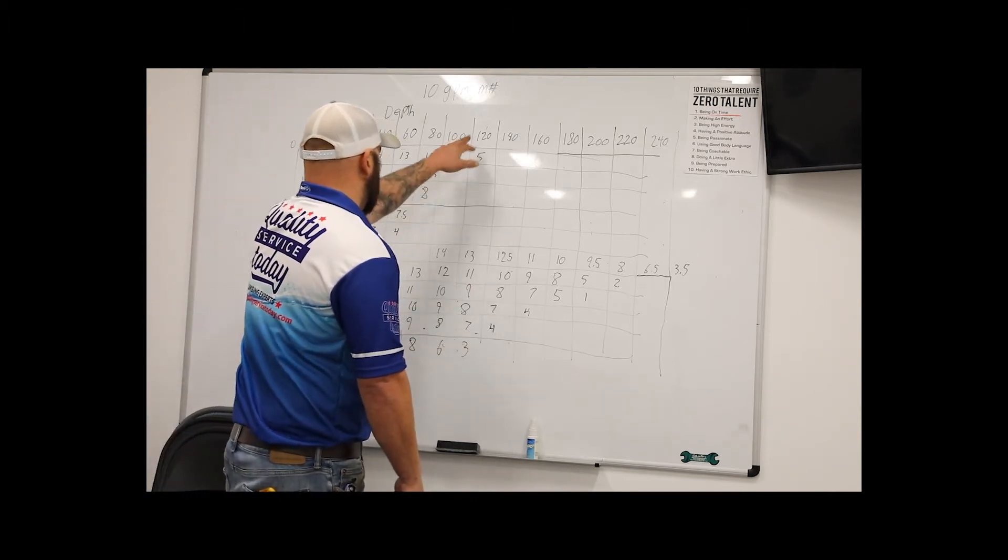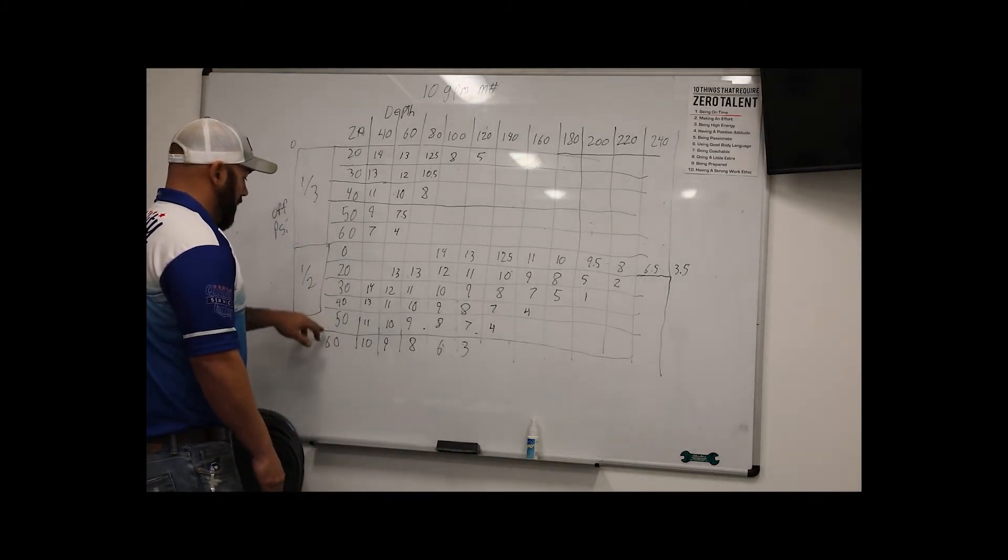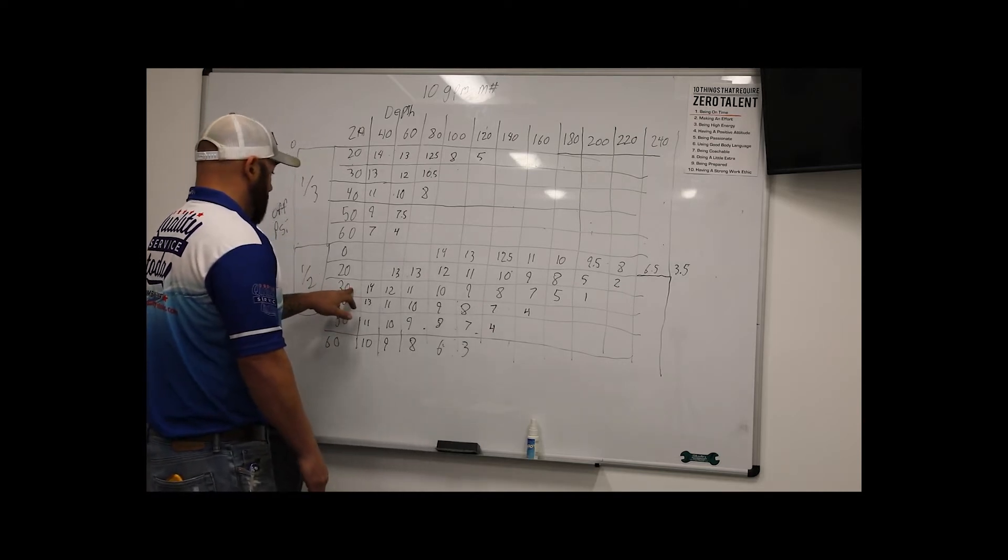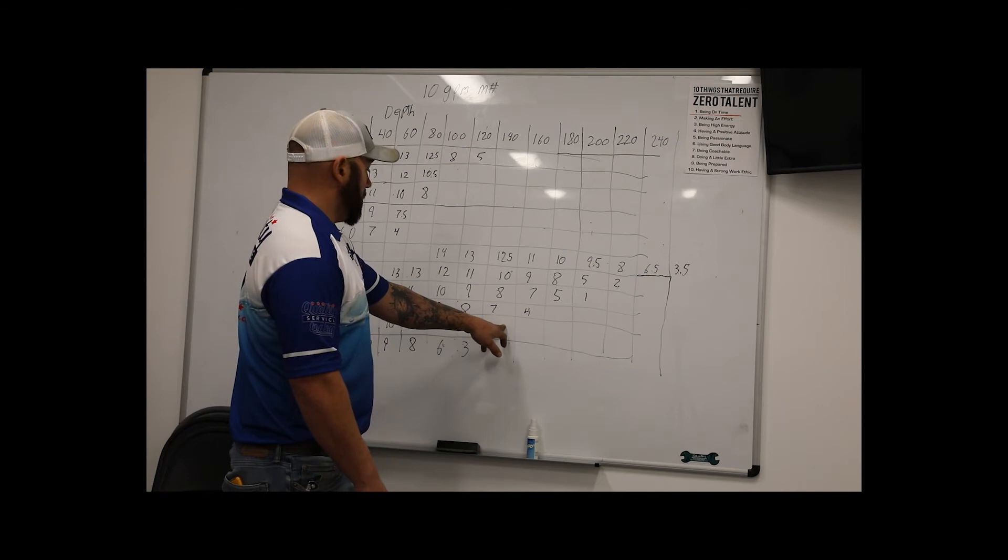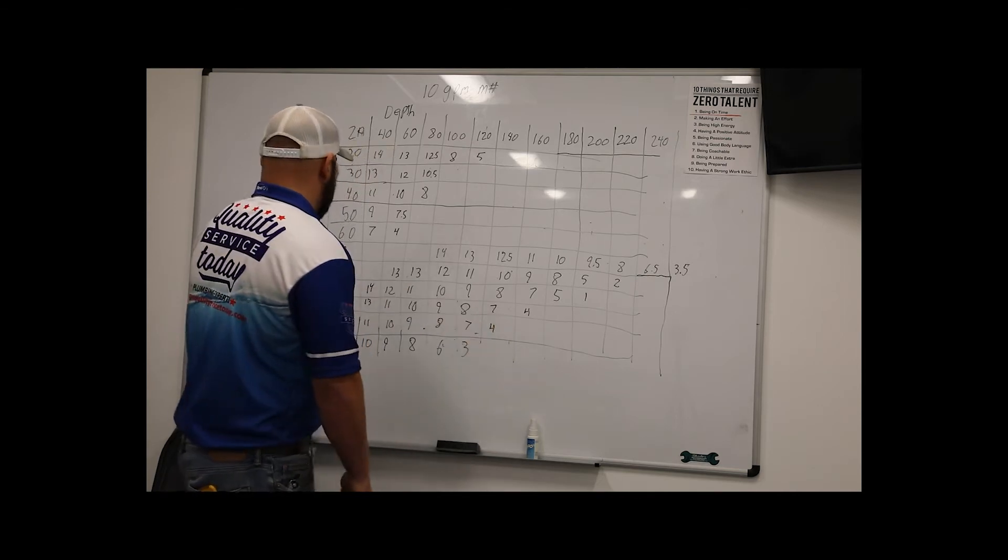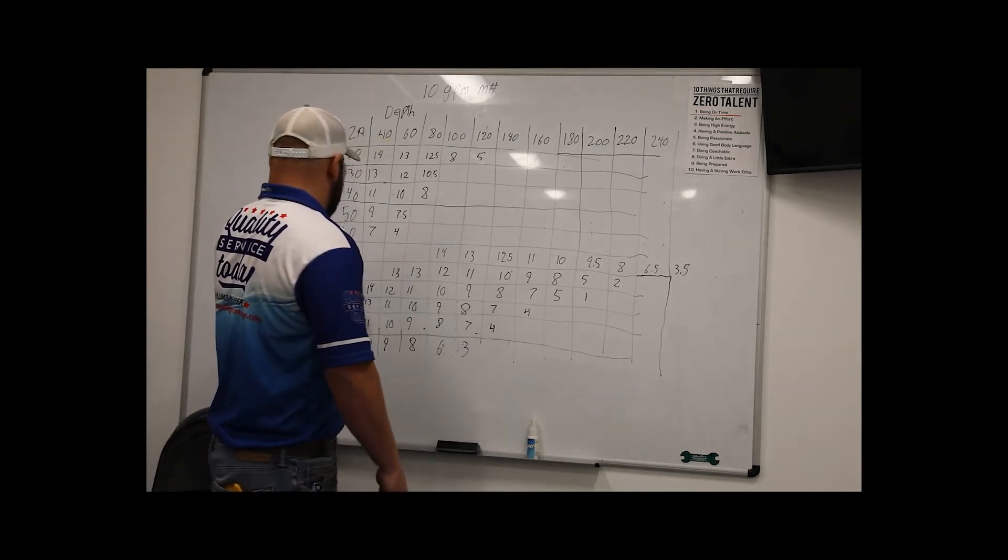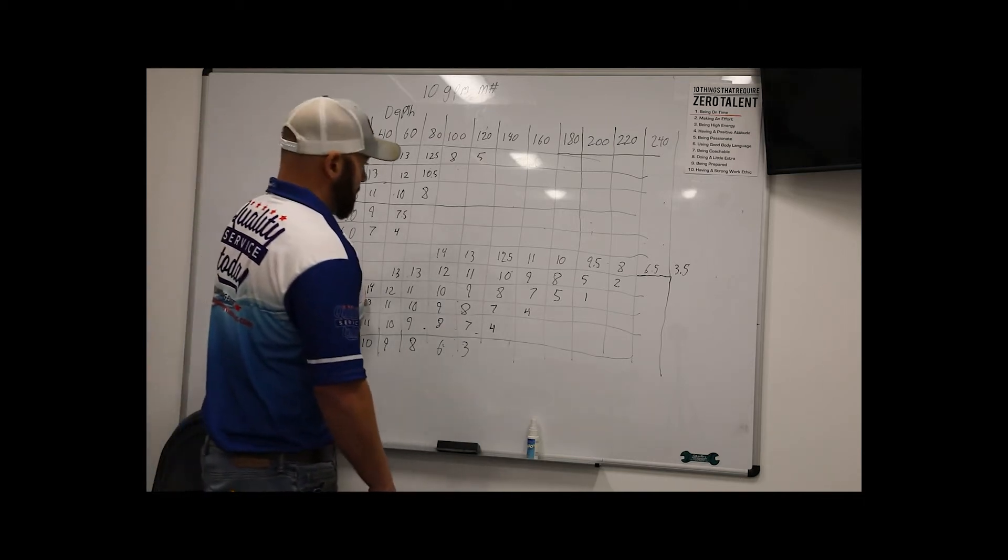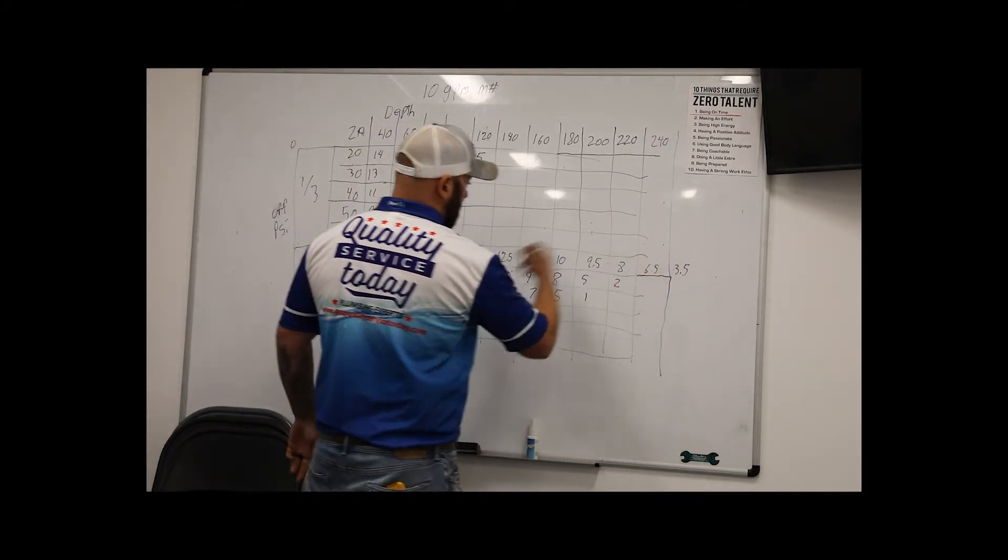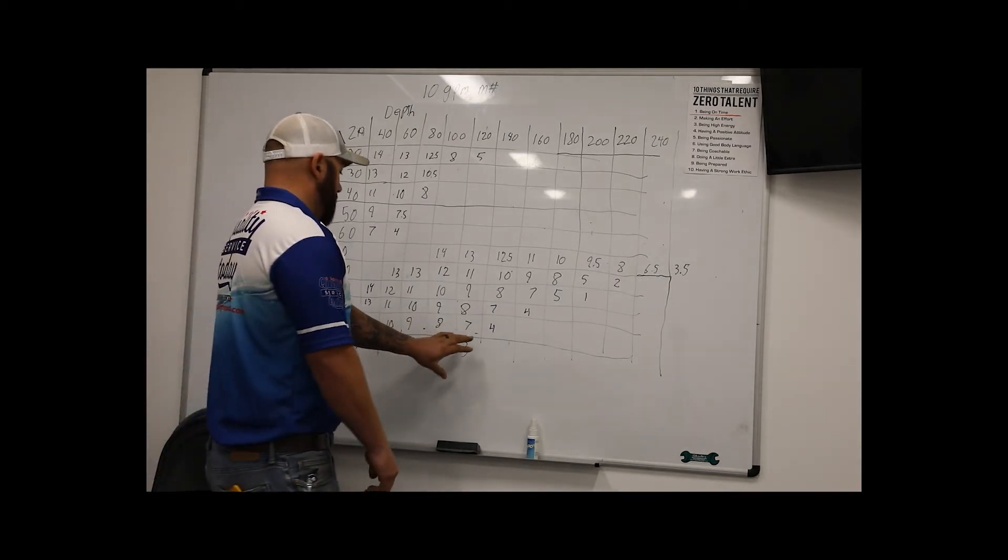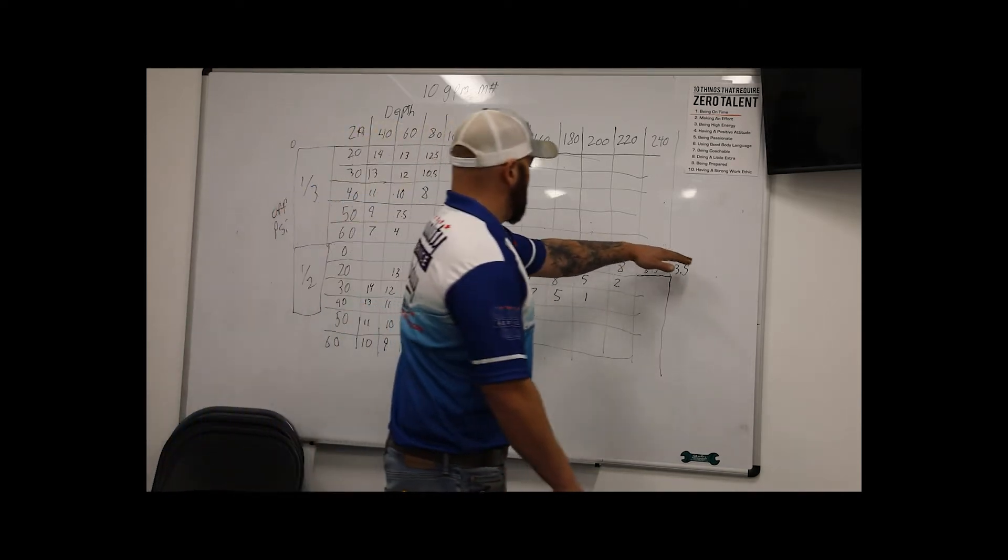So, 3 gallons a minute at 120 foot. Now, if we reduce our shutoff pressure, typical switches are 30-50 and 40-60. On, off, on, off. If we reduce our pressure to a 30-50, we can move up from 120 to 140 foot at 4 gallons a minute. As you see, as this gets shallower, if we had an off pressure at 20, which you're not going to, I mean, but hypothetically, you could hang that at 260 foot deep at 3.5 gallons a minute. But that just goes to show how this increases. The shallower we go and the less pressure, we can hang it deeper.